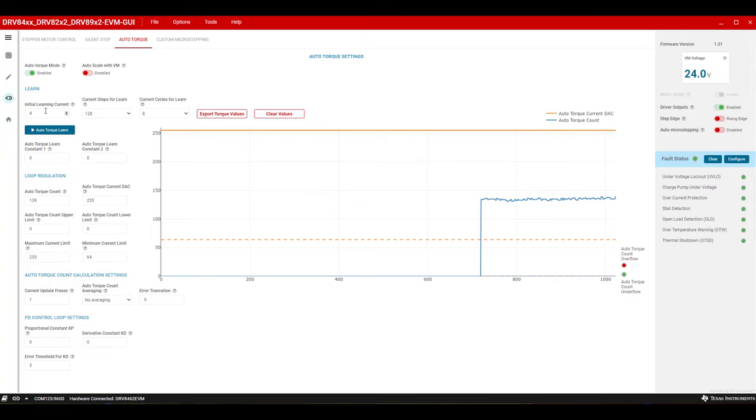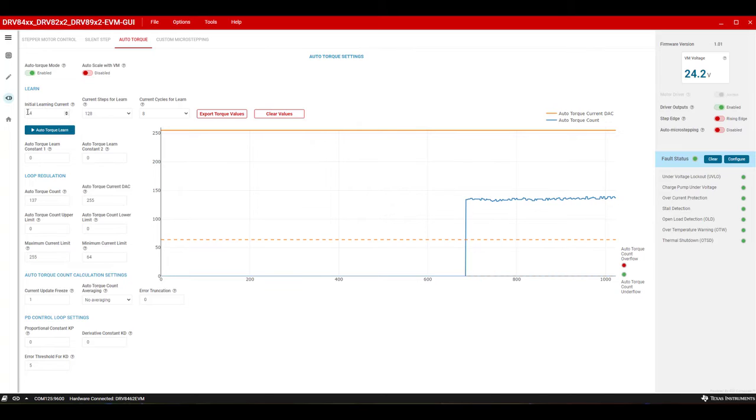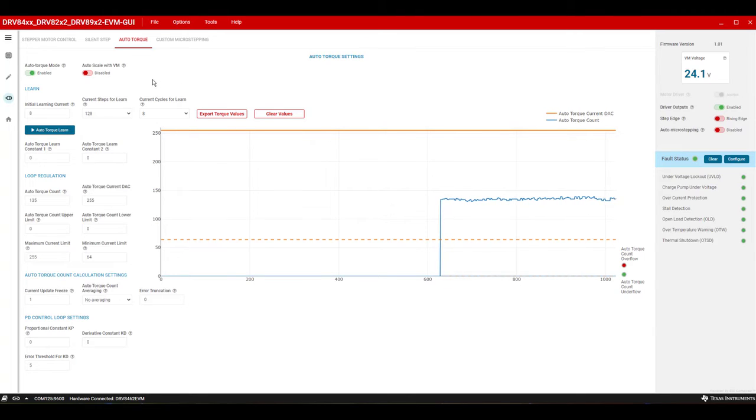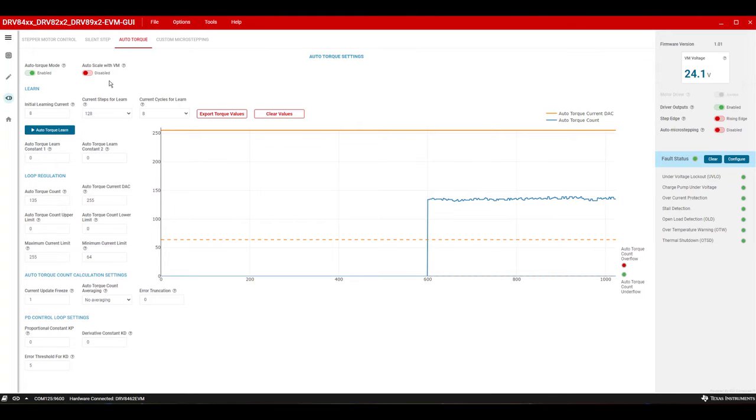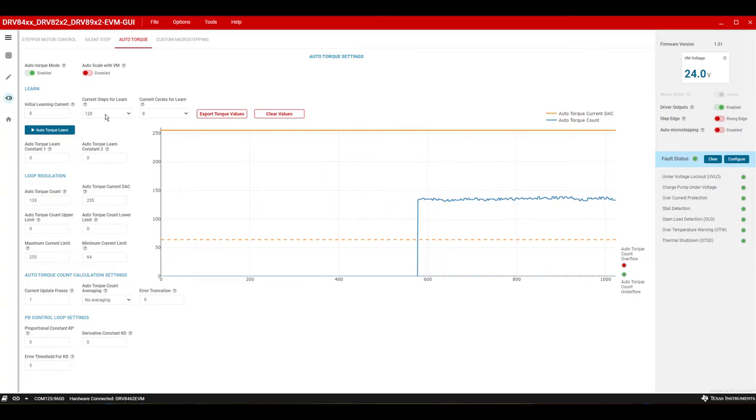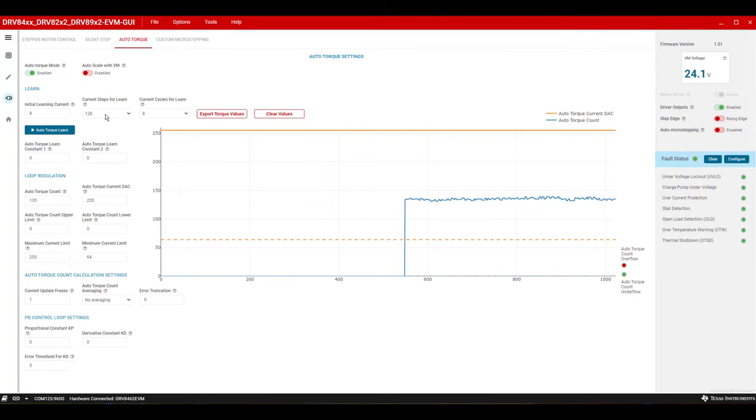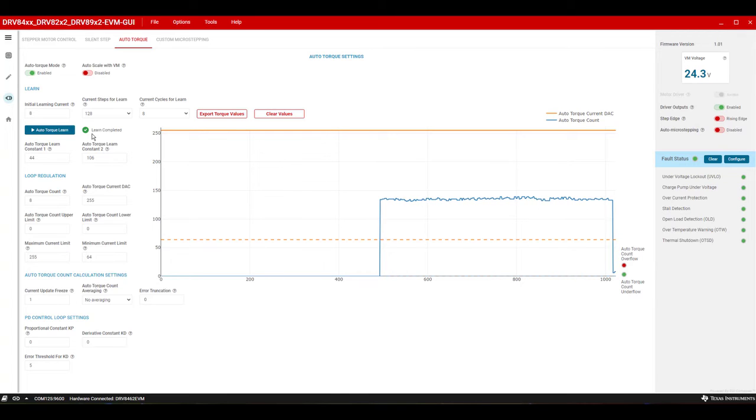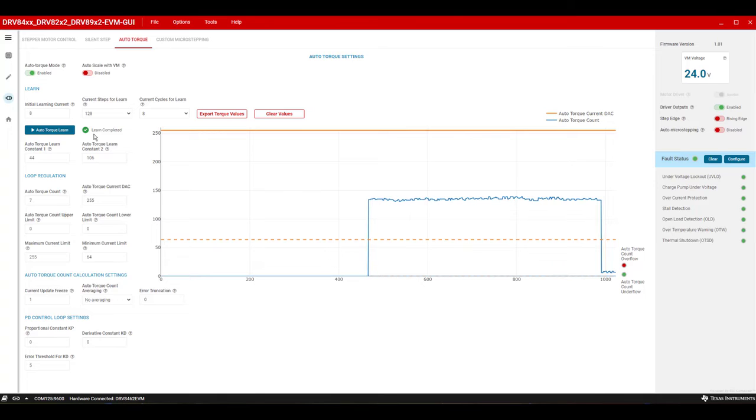Next, the initial learning current setting. Set this to 8, just so times 8 of this value is greater than or equal to 64, the minimum current limit setting. The current steps for learn can be at the default value of 128 for this setup. Start the auto torque learn by pressing the button. Completion of the learning procedure is indicated by a learn completed check mark.